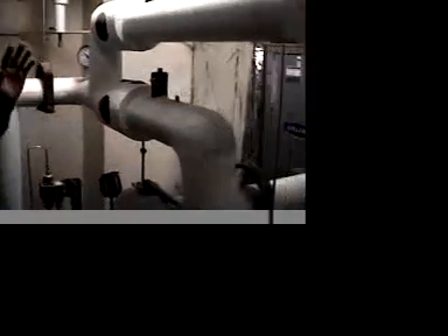That's how the controls will be set. Now what's going to happen is that when there's a freeze stat serpentined on the coil, and the temperature reaches a point on the coil that it's below freezing, the dampers will shut down and you'll go into an alarm mode, and Johnson will identify that this air handler is off. You're in a low temperature mode in the air handler and you need to do something.